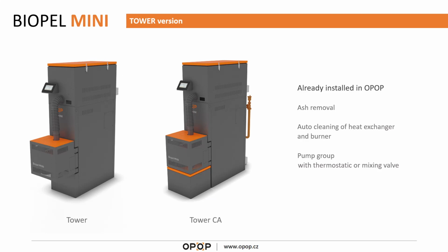As we mentioned, we also have a tower version, which is also available in the plus version or plus type of setup. So you can still choose, even with the tower version or compact version or with the external hopper, it doesn't matter. Every single setup can have the plus version, which means that the ash removal system, auto cleaning, and pump group with thermostatic or mixing valve are already installed on the boiler by us in the factory. You can still buy these accessories separately.